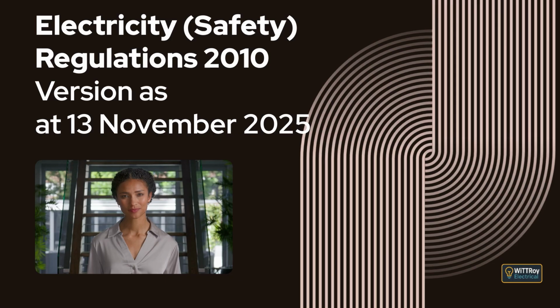Reg 62, high-voltage installations treated as if works. This regulation explains that all installation, testing, inspection, and connection work carried out on a high-voltage installation must be done in accordance with a certified design prepared specifically for that installation. It also explains that, unless this part clearly limits how it applies to high-voltage installations, Regulations 34 and 39 to 46 apply to high-voltage installations in the same way they apply to works, with references to works treated as references to high-voltage installations. We'll now look at testing prescribed electrical work.